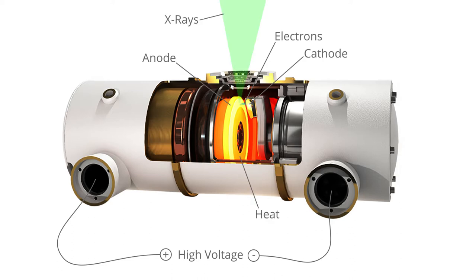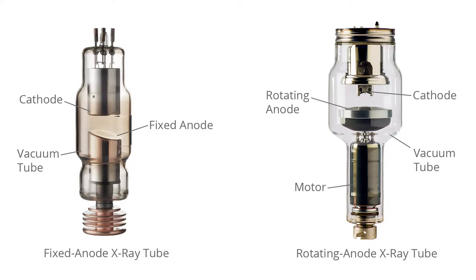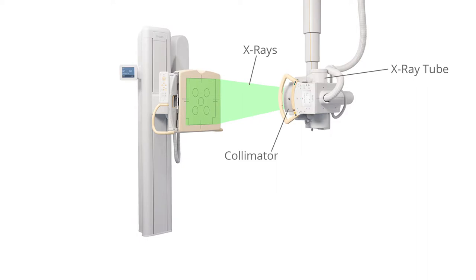The x-rays go through the patient and some of the radiation is absorbed. Denser structures such as bone absorb more x-rays than softer structures. The voltage of the x-ray tube and the material of the anode determine the energy of the resulting x-rays. The collimator focuses the x-ray beam by allowing only x-rays traveling in a certain direction to pass through.